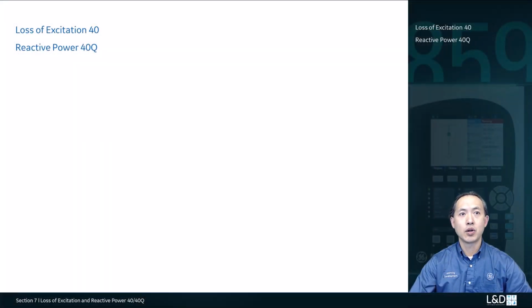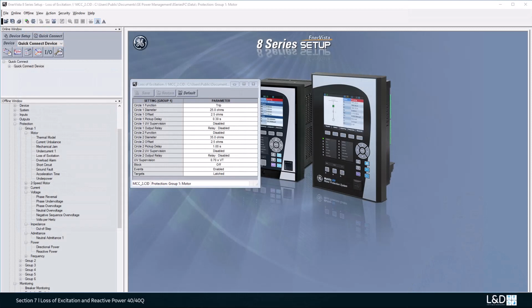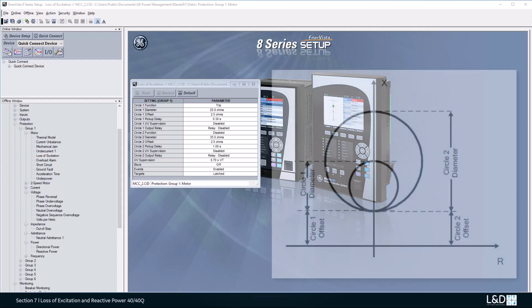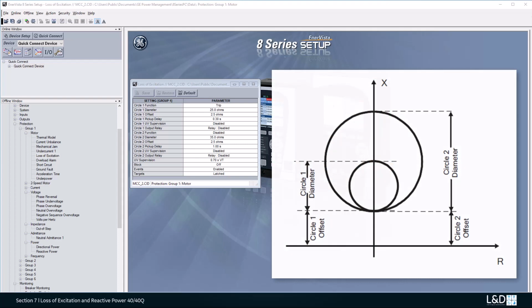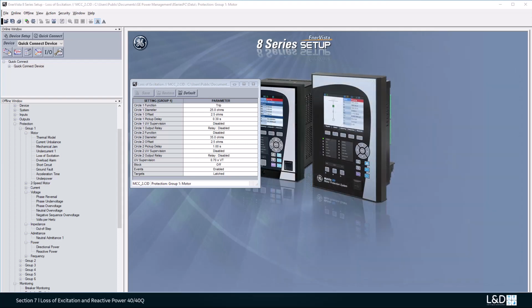In this session, we'll cover the loss of excitation 40 and reactive power 40Q. The loss of excitation protection is applied to protect synchronous machine from overspeeding, as well as to recover system from voltage collapse. Loss of excitation protection is achieved using the positive sequence impedance measurement from voltage and current, and two inverted offsets, Mho circles. In the case where the circle element is enabled and measured positive sequence impedance falls within this circle, the element operates with the corresponding time delay setting. For the equations of the calculation of the two Mho diameters and offset, please refer to the instruction manual.